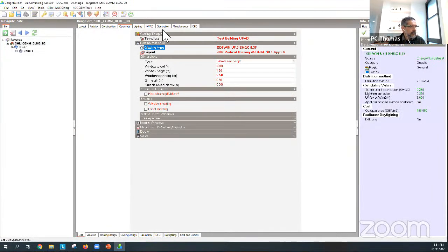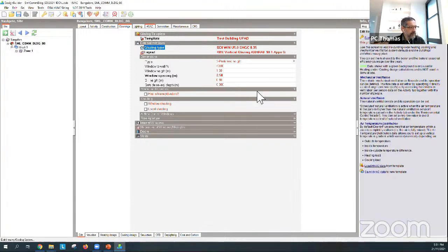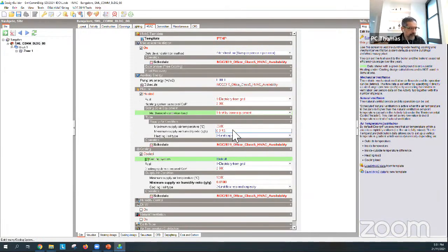And you can do things like oversize your air conditioning system slightly to capture most of those details. Here the problem is that we don't have zoning, so it's looking at an average temperature across the whole floor plate. It's a very hard thing for the air conditioner to do, because at any one time some part is going to be too hot or too cold. In this case, hot. So hopefully we've covered what we need for air conditioning.